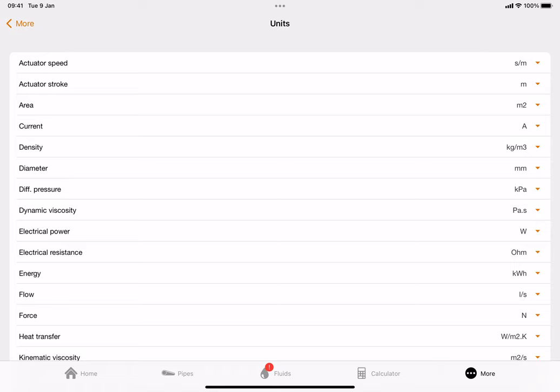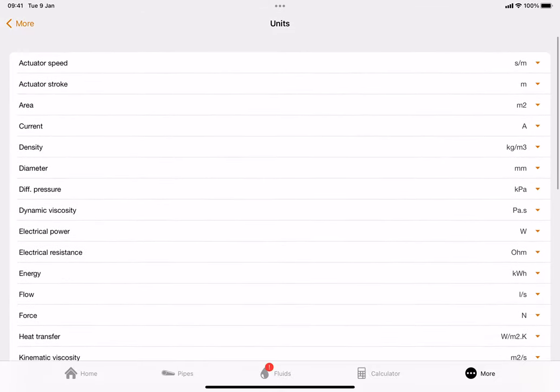You can copy all of them that are on my screen - just click on them and make sure they look exactly the same as mine. Pause the video if you want to catch up. The important ones are: differential pressure in KPA; energy, which is also very important, in kilowatt hours - if you want to change them you just click on the energy one and it will give you the different dropdowns. Flow we want in liters per second.